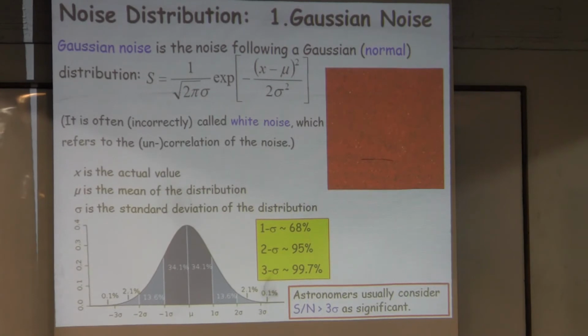Now, an example here is if you take a nice flat detector and read it, say you take it in the dark, so you have no signal on it, but you will get values from the individual pixels. They're all around a mean value, right? The mean value here probably corresponds to something like dark red. But there is some scatter here, right? Some pixels, like the yellow ones, are above this mean value. Some of the darker pixels are below this mean value.